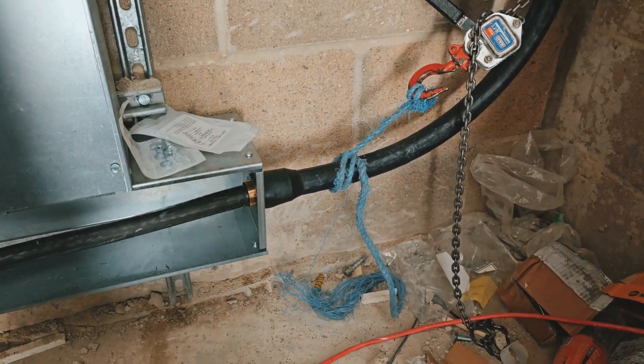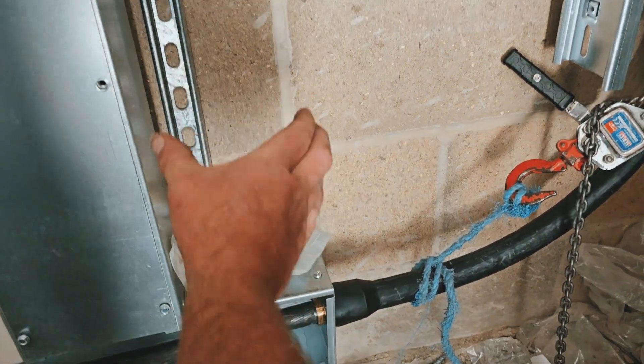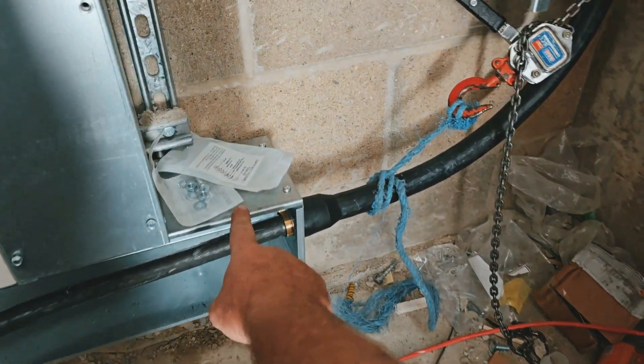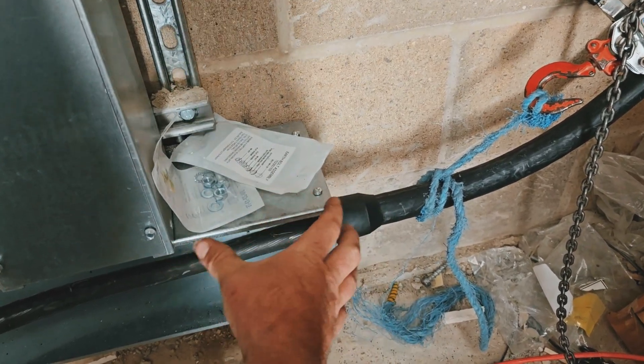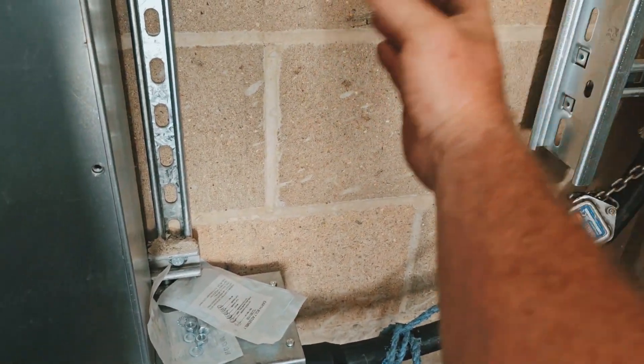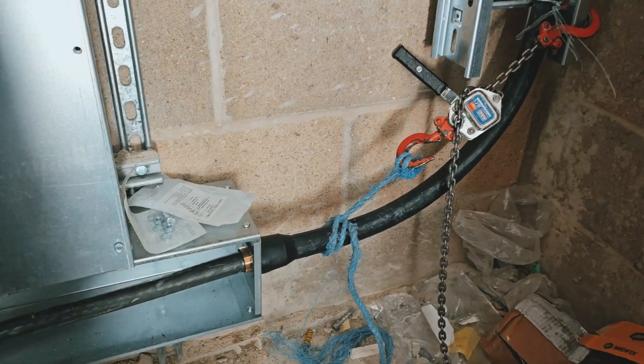Just take off the end plate. In any situation like that, if you're in a tight situation you can actually request — if it's coming down — to put a little T-piece up there with a clamp with the end plate on, and you can take everything off and just push it back. So that's a thing to remember: request to the electricians that instead of just having a flat end, if you haven't got a lot of room, put a T-piece in with a piece coming up the wall. You can then gland the cable and push it back without having to pull all the cable out in limited room. It's only four bolts and you can put them back in quite easily.